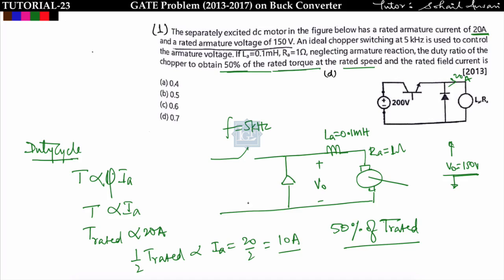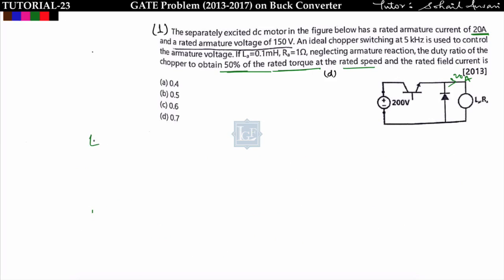We have to find the duty cycle for which armature current is 10 ampere. First, find the back EMF: E = V0 - Ia × Ra = 150 - 20 × 1 = 130 volt, which is constant. For 50% rated torque with the new armature current of 10 ampere, the new V0 = E + Ia_new × Ra = 130 + 10 × 1 = 140 volt. Therefore, duty cycle = V0_new / Vs = 140 / 200 = 0.7.